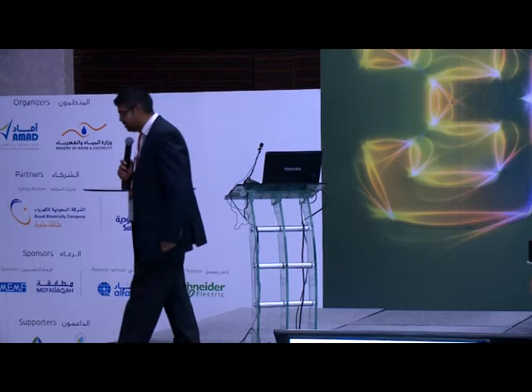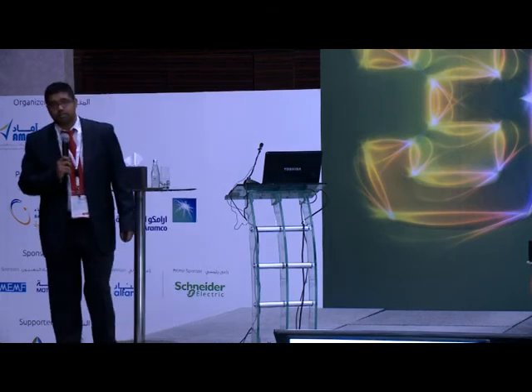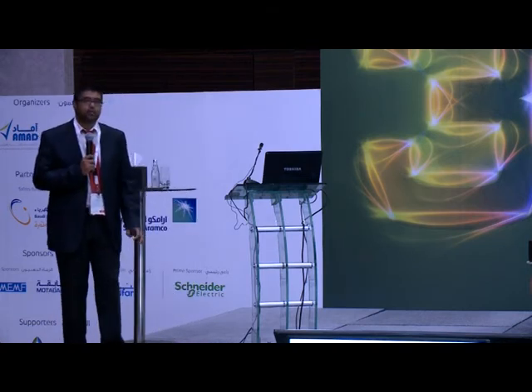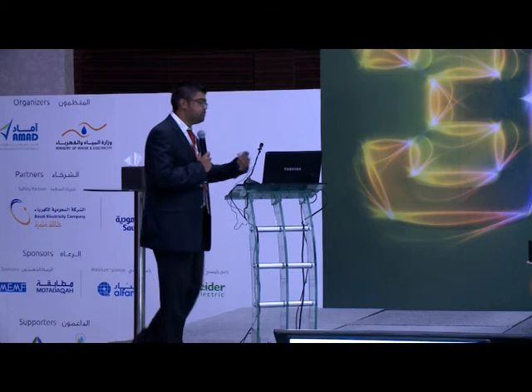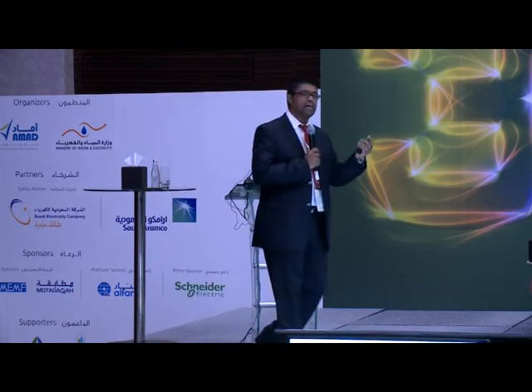All right, habit number 4 is the use of earth leakage or ground fault interrupting circuit interrupters. I'm not going to speak about that much. Now, habit number 5, I just want to spend a minute and a half on that. Habit number 5 refers to creating an electrically safe work condition. And when we speak about an electrically safe work condition, what eHazard has done is we've come up with a very simple acronym called ISOLATE.